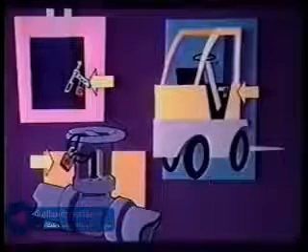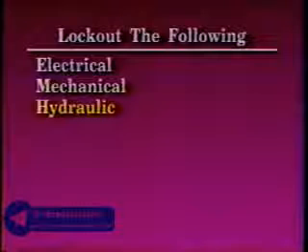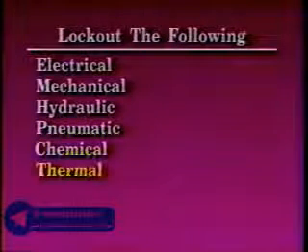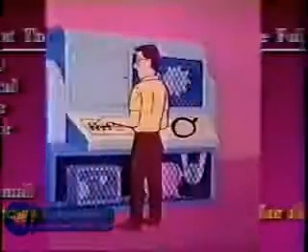Lockout is more frequently thought of in connection with electrical switches, because that's where they're commonly used. However, lockout-tagout systems shall be used to isolate all energy. The lockout program shall address all types of energy. The WAC standard requires the following sources to be locked out: electrical, mechanical, hydraulic, pneumatic, chemical, thermal, gravitational, and stored energy for all of these.